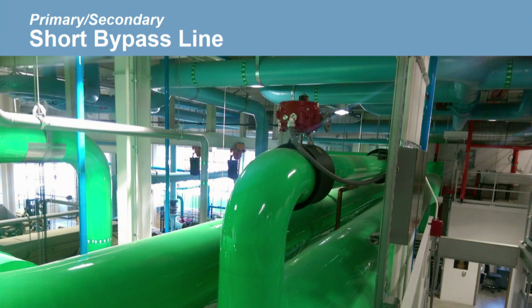diameters long. If the bypass line is too short, again, there is very little pressure drop and the water tends to short circuit. This causes issues similar to the oversized bypass line. So if your supply and return manifolds are close to one another, one option is to put an orifice in that bypass line. But sometimes the distance is too small.